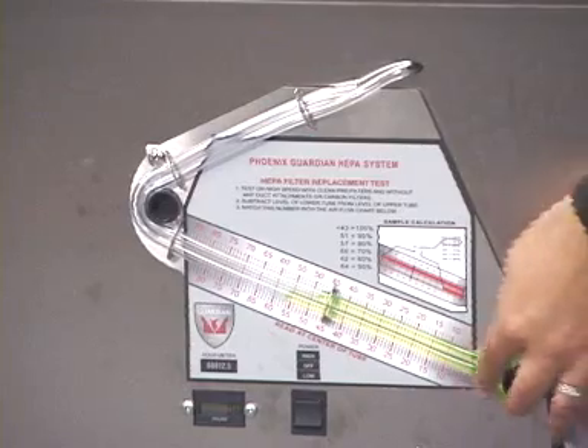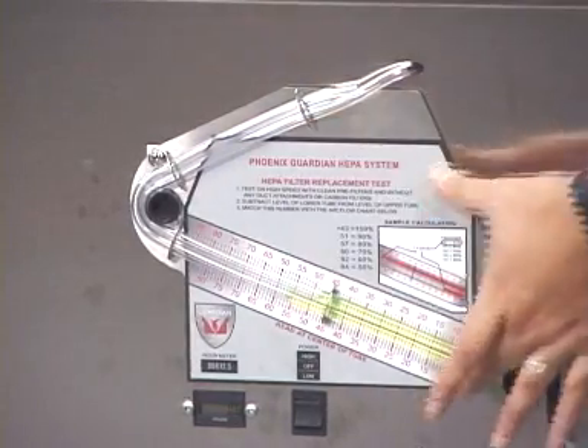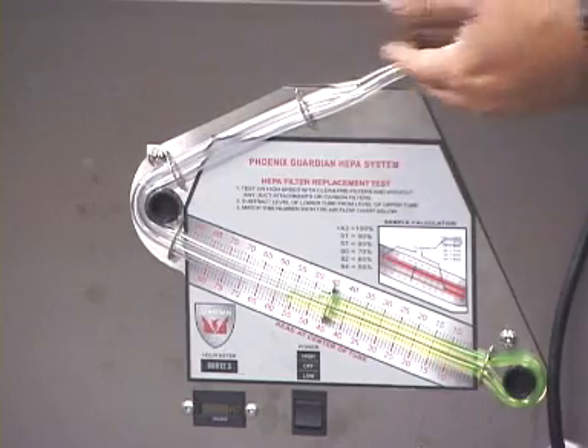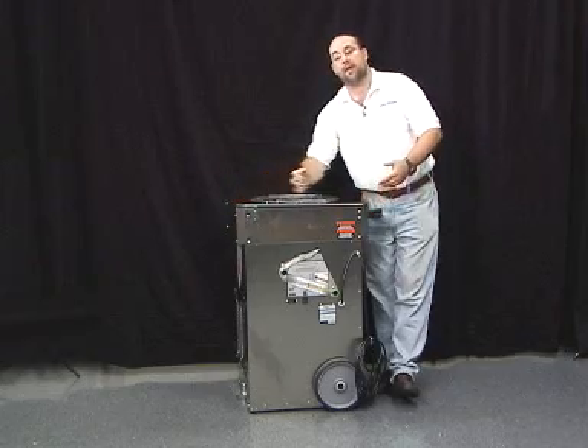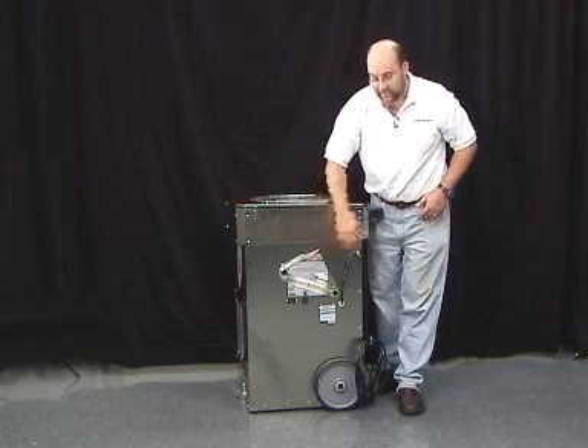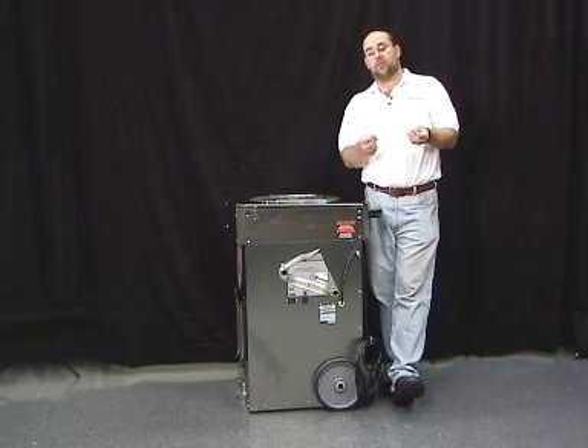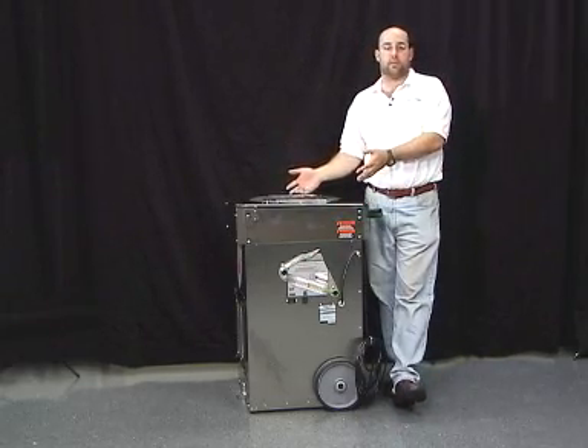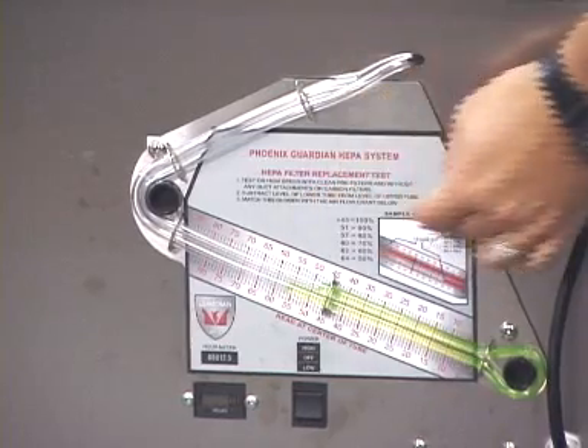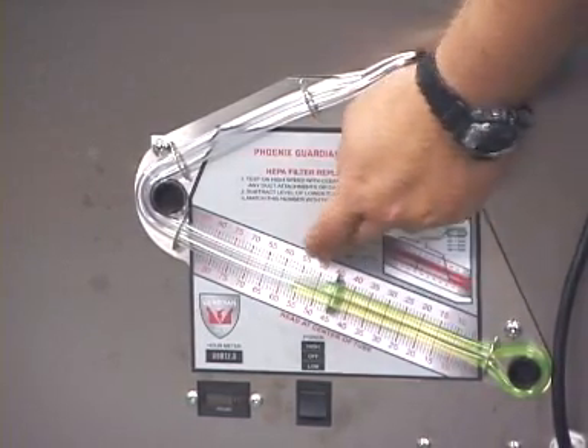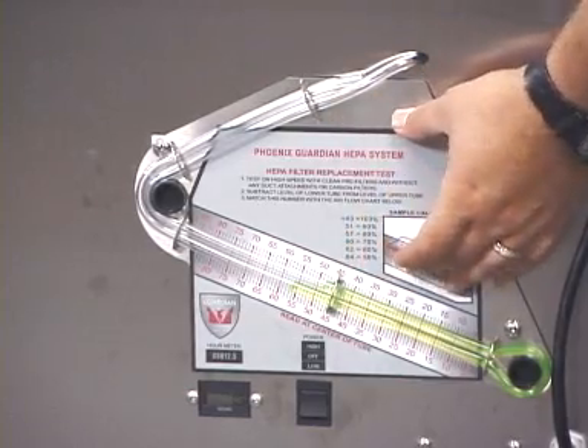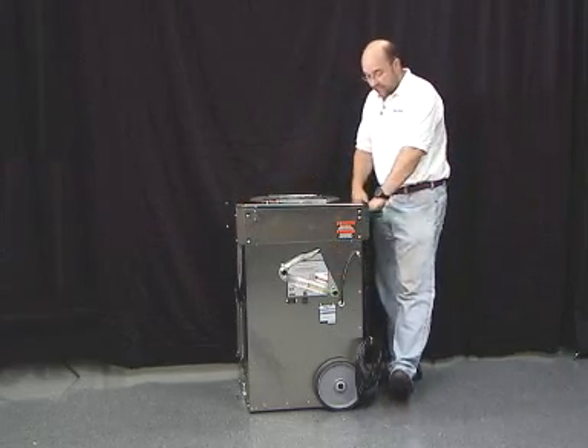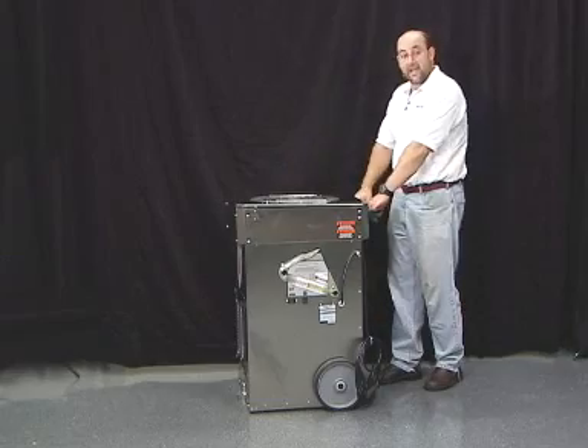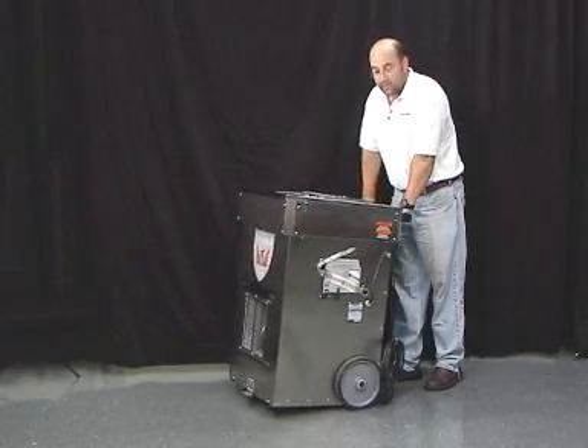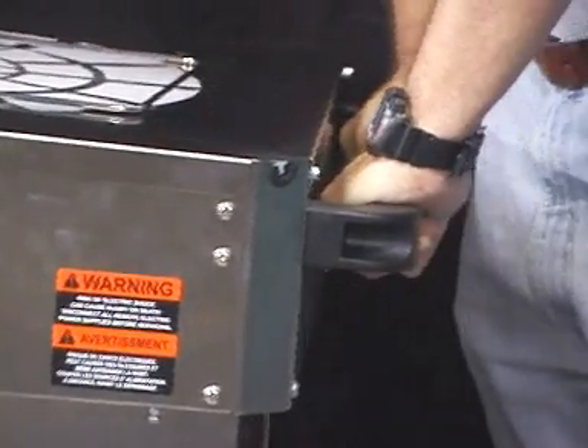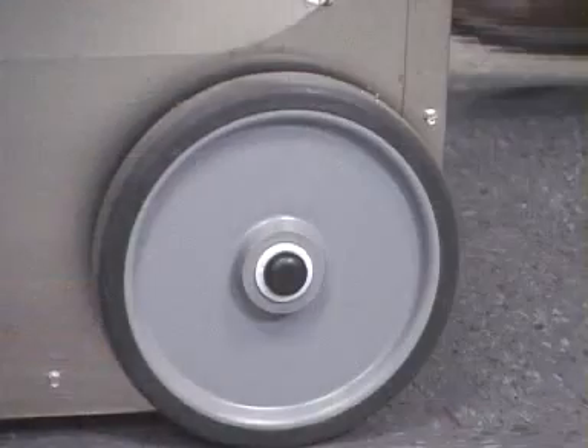Another feature you'll see on the side of the machine is this tubing along with an instruction guide panel. This is what we refer to as a manometer. The benefit of having this on the machine is it will allow you, the technician, to determine when the HEPA filter needs to be replaced. It also has a great little instruction guide that shows you how to read the tubes and determine your HEPA filter efficiency. Working our way to the back, the machine has a nice wide handle, making mobility relatively easy, pretty easy to get through doorways, and it also has nice larger wheels.